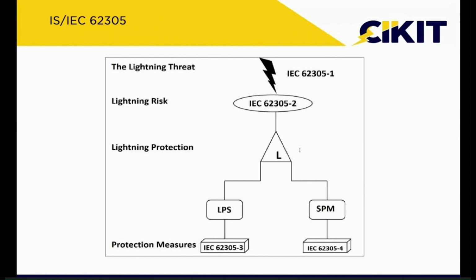So usually for the oil and natural gas industry, we'll be considering either level 2 or level 1. Then based upon the risk level, we'll be designing what will be the suitable level of protection. So if you take this risk assessment calculation, there are mainly two outputs. One output is whether lightning protection is required or not, and the second output is what should be the suitable level of protection for this particular site condition.